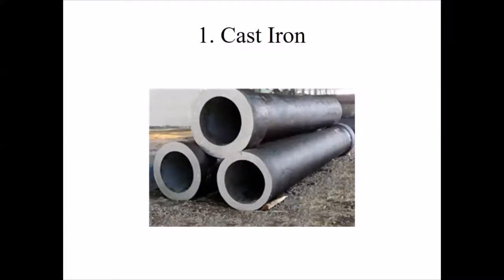Cast iron pipes are manufactured from pig iron by casting, or molding. These pipes can resist corrosion and can withstand high internal pressure, but they are very heavy and difficult to transport. The pipes are brittle in nature and may develop cracks if handled carelessly. They are suitable for conveyance where internal pressure is very high.